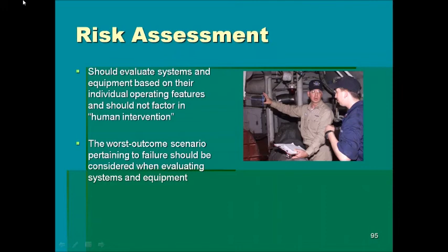But back to that risk assessment. You've got to make sure that you're doing a risk assessment that will determine, based on the types of systems and equipment that are regulated by NFPA 99, what the consequences would be if that system fails. If your electricity goes out, including your generator, if your plumbing or your HVAC system goes out, you've got to speculate what the worst outcome would be, and then you've got to determine a risk value associated with that outcome.